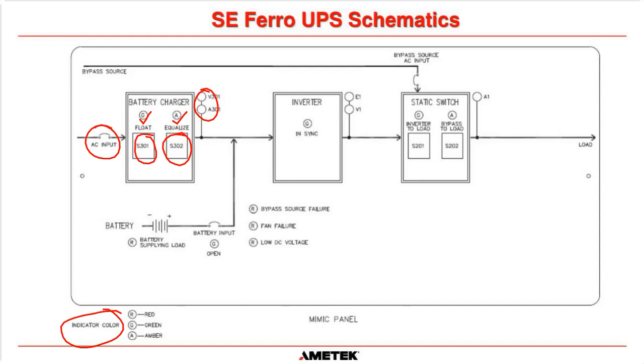We have a sensing circuit inside the system that measures if the voltage has dropped below 127 volts for a 60 cell system. If the voltage measured there goes below 127 volts, then this red alarm will come on saying the battery is supplying load, because in normal operation, the battery should not be supplying load. This one here can be a bit confusing. I'm not quite sure why we made that LED green, because the battery input breaker open is not normal, so it should not be green, in my opinion. But it is. So if you see this light on, then that's telling you that the battery input breaker is open.